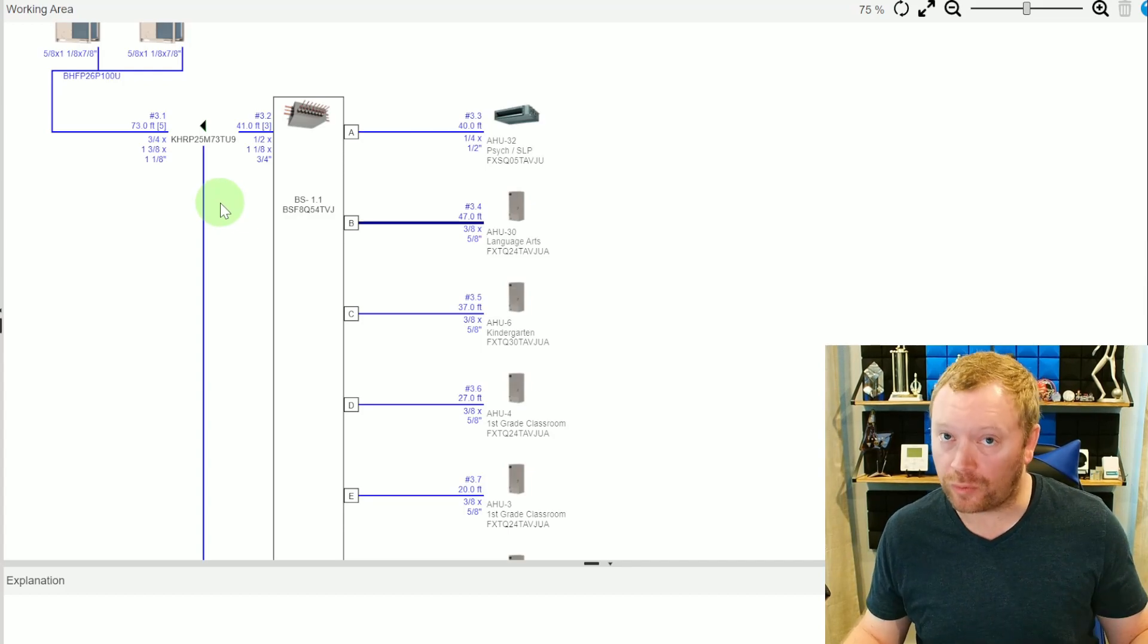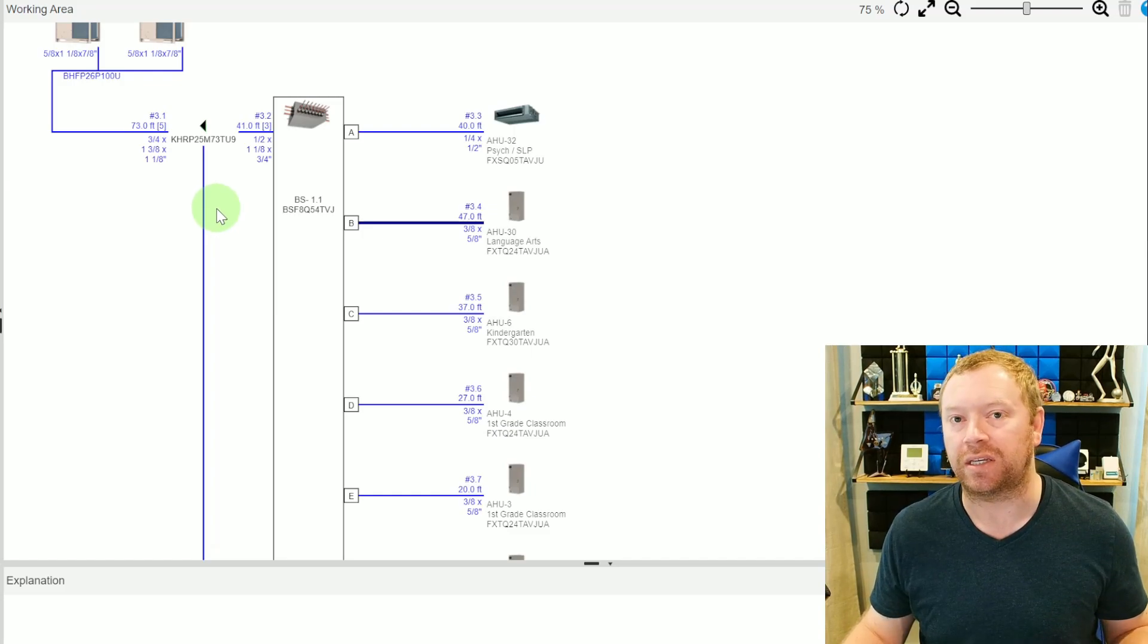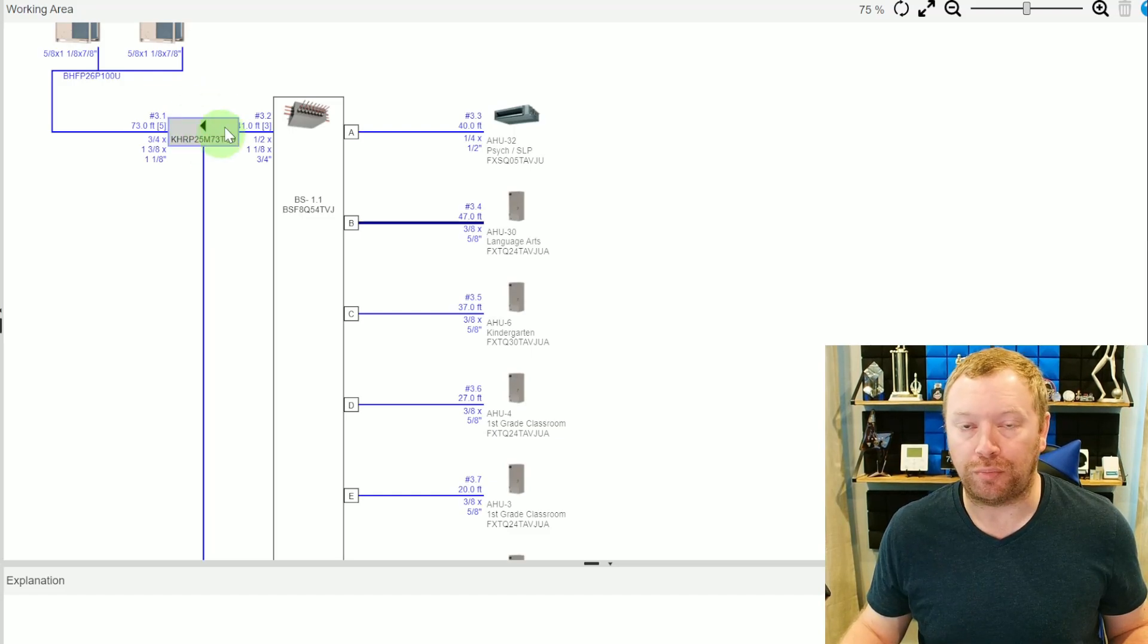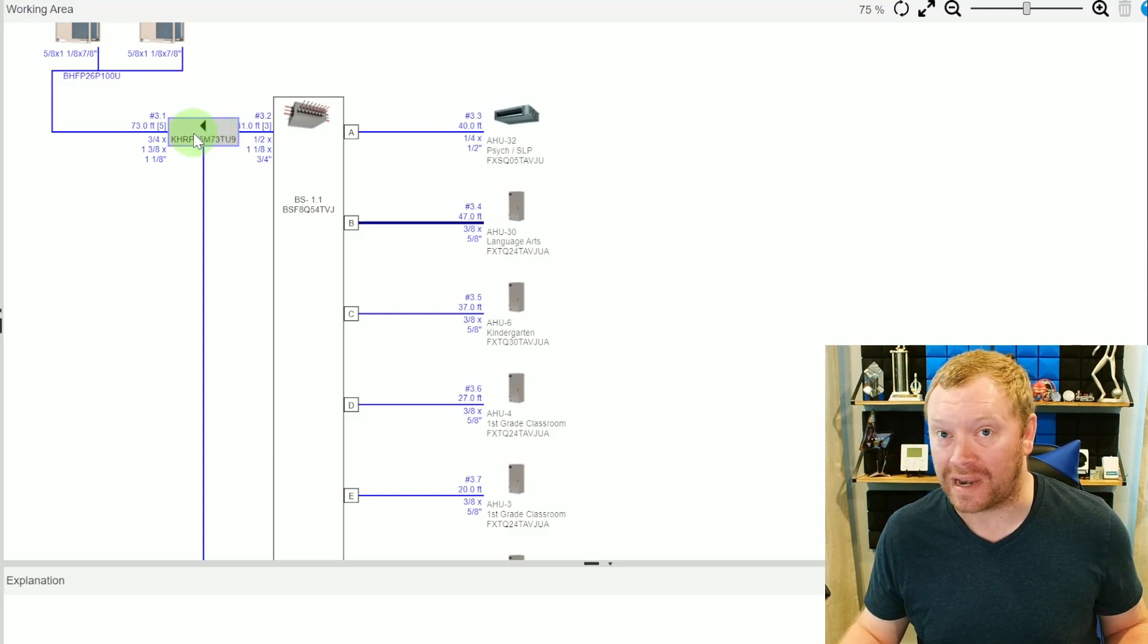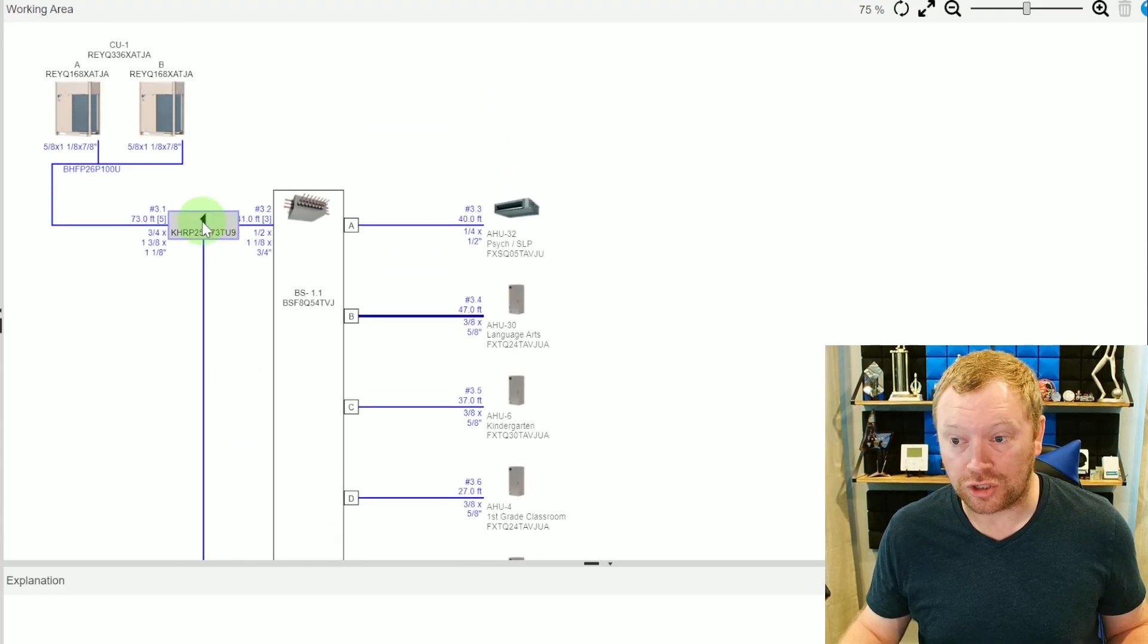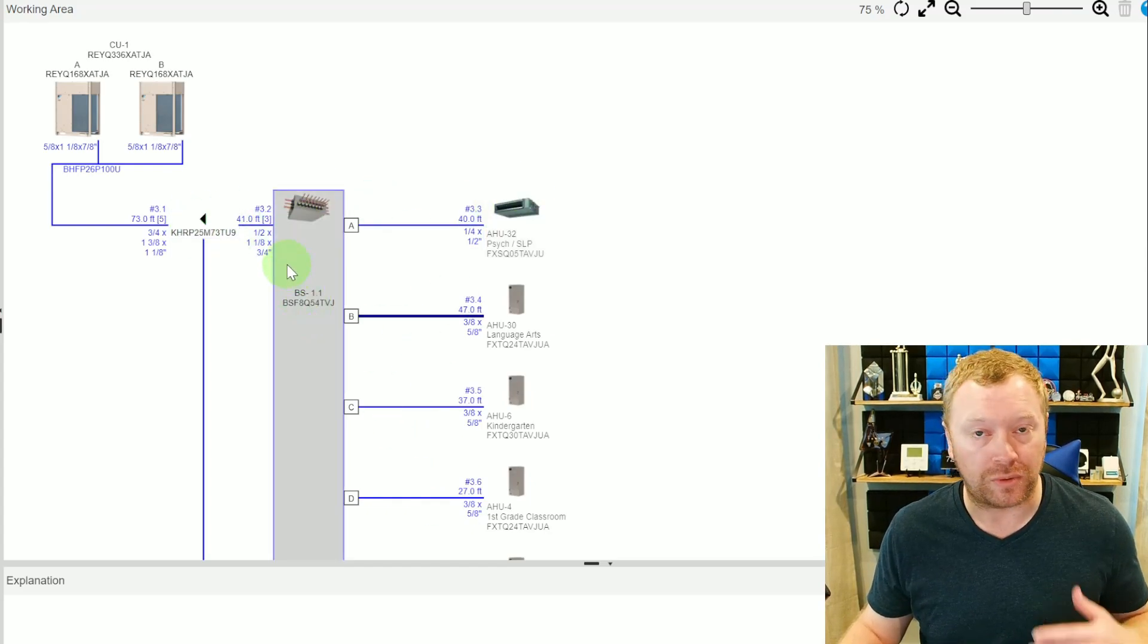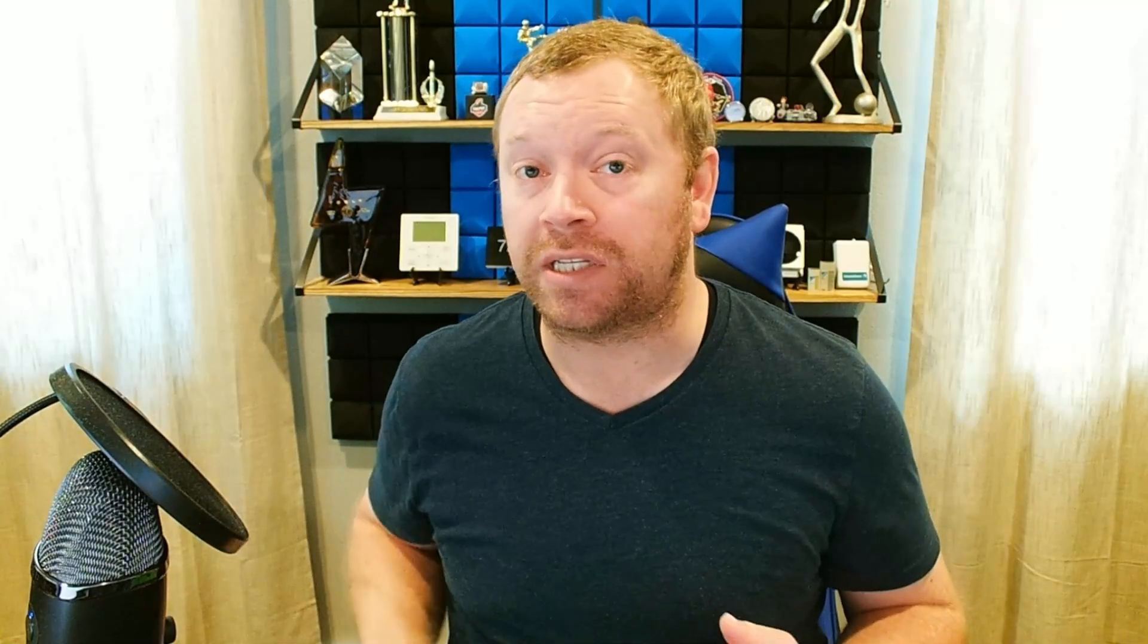Anytime you guys are doing installs, the best rule of thumb that I always tell my guys is the rule of 130. There's a lot of other rules to consider that are also important, but the one that always kills us is 130 feet from your first branch that you put on your system. That's this KHRP. We call it a refnet refrigerant network Y branch. It splits off our main line to go to multiple branch boxes shown here, this to the furthest indoor unit. So from this branch to this box and from this box to each indoor unit, you can't exceed 130 feet. And if you do, you need to upsize the copper.